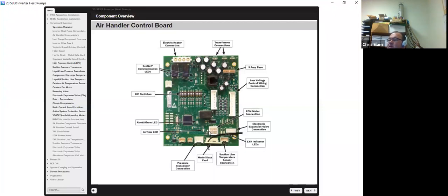You have your ECM motor connection, your EEV valve connection. We have 2 little lights here that will tell you what your EEV is doing. It's opening or closing. Green is opening, red is closing. Here's your suction line temperature sensor connection here. This is what your model data card will look like. And you kind of see here it's got a zip tie on it. That's there for a reason. You have your pressure transducer connection. You also have your airflow LED, and then you also have your alert or alarm LED.